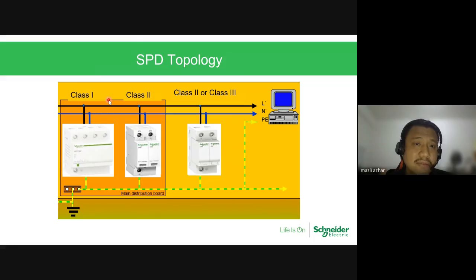How it is installed: class 1, class 2 first, and then class 2 or class 3 before the equipment. So if there is a lightning strike or surge, these two will cater first; they will divert to earth or limit it. And then if there is excess, this class 2 or class 3 will take into play, whereby it will also divert or limit the current voltage going to the load or sensitive load.